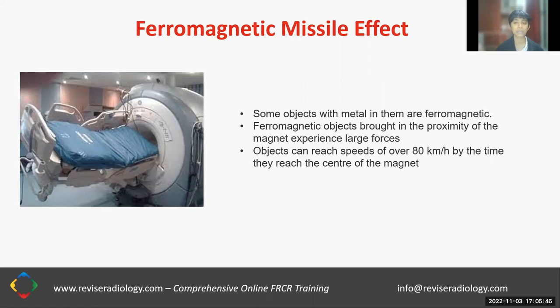When these metals are brought close to a magnet, they experience forces which are several times the force of gravity. These objects are pulled in a certain direction, and can reach speeds of over 80 kilometers per hour by the time they reach the center of the magnet, which is generally where the patient's head is positioned. This is called the ferromagnetic missile effect.